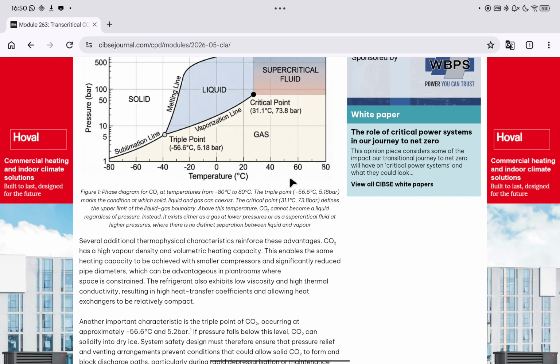Several additional thermophysical characteristics reinforce these advantages. CO₂ has a high vapor density and volumetric heating capacity. This enables the same heating capacity to be achieved with smaller compressors and significantly reduced pipe diameters, which could be advantageous in plant rooms where space is constrained.